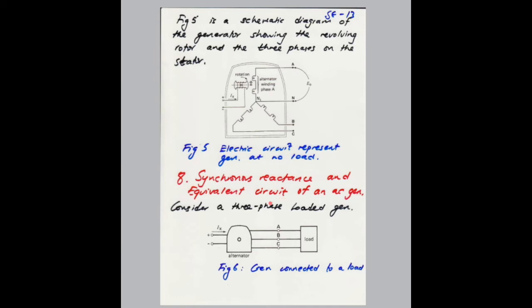So we will start with this figure 6, which is showing you a machine. Remember, it's got a shaft that's being driven by a turbine. And what's happening is you are feeding a current, a field current, to the rotor, and that interacts with the stator, and obviously then it induces voltages onto your three-phase terminal of the stator. And if you connect a load here, it will receive three-phase power.